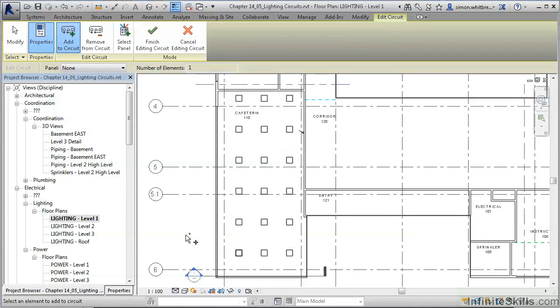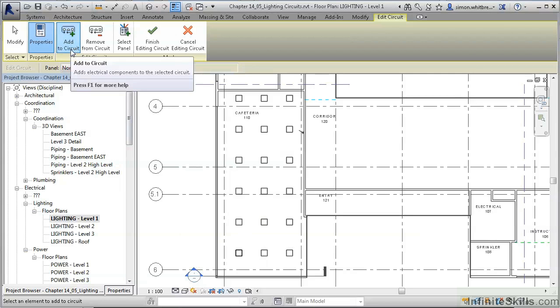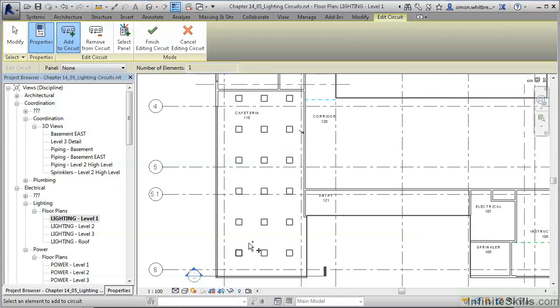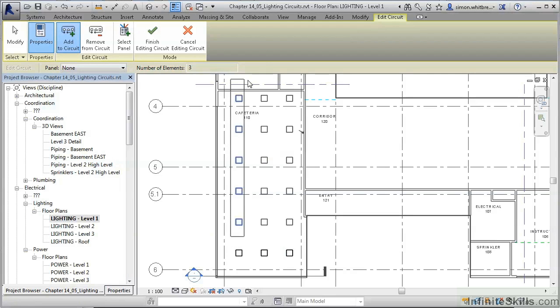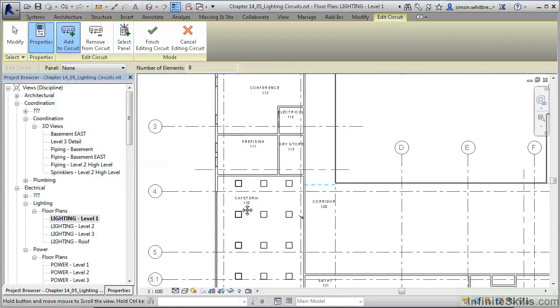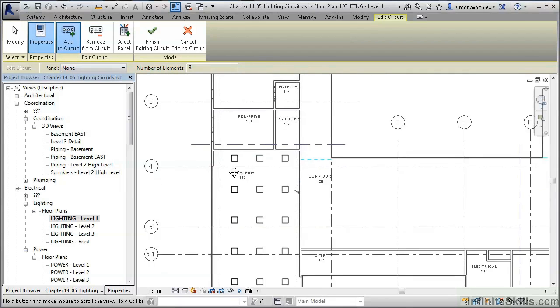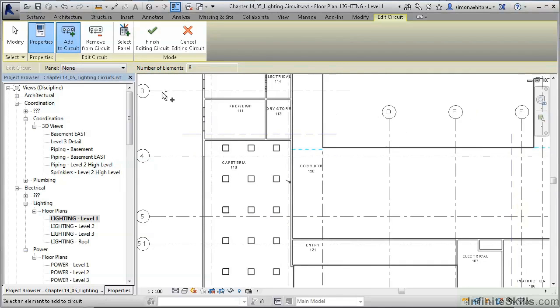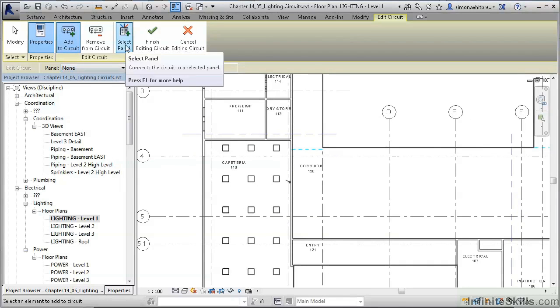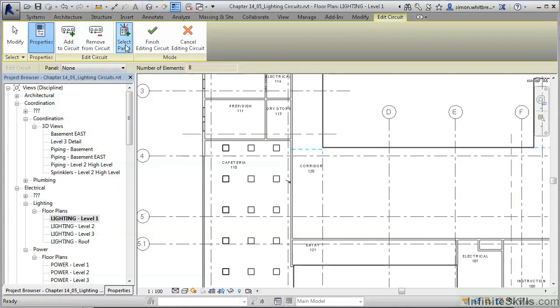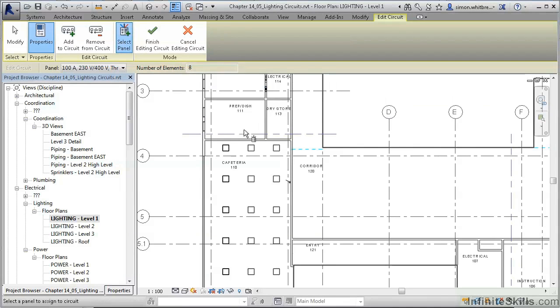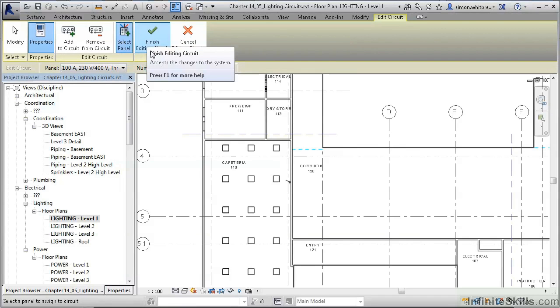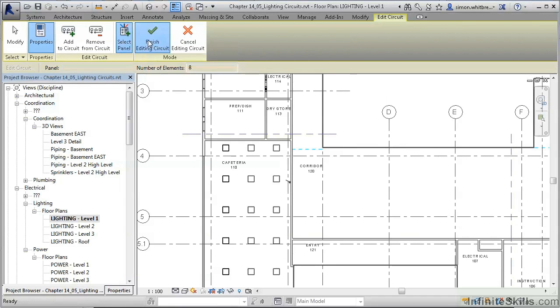In the cafeteria, I am going to make two circuits: one for perimeter lighting, the other for the rest of the lighting. So in Add to Circuit mode, I am going to select all the perimeter lights using a selection window. Once selected, we can then click on Select Panel and select one of the panels from the electrical room. Now that we are complete, click on Finish Editing Circuit.